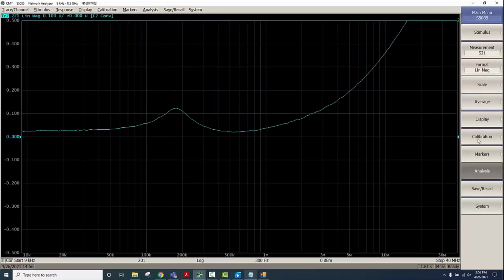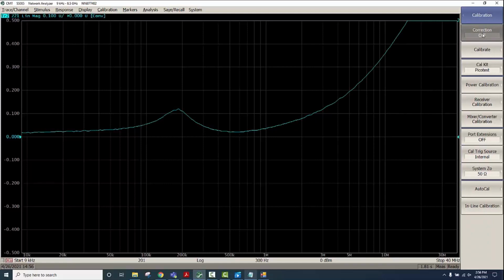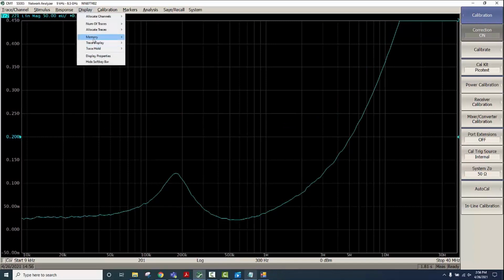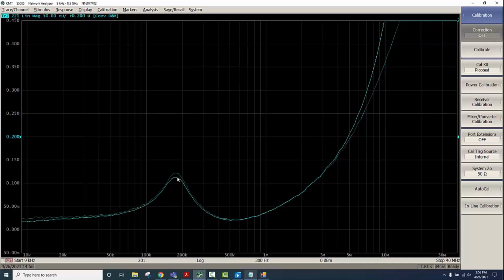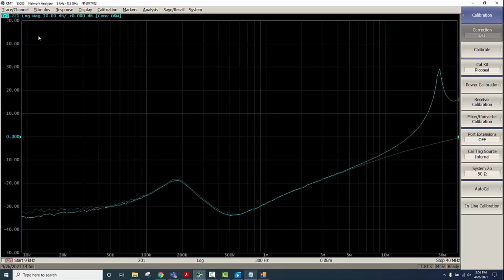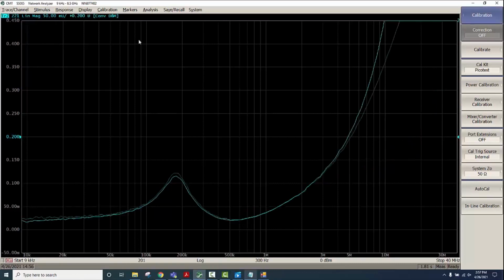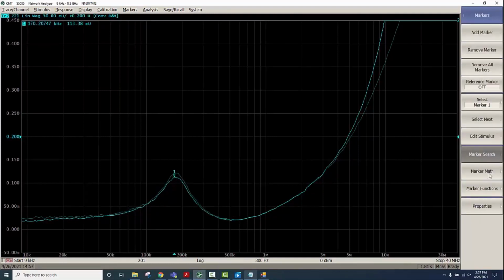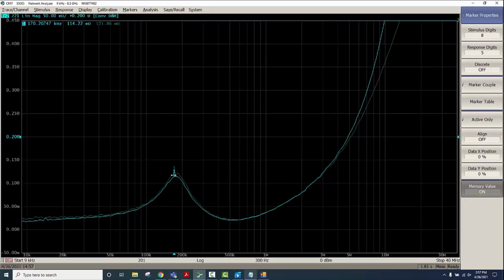We can also look at the measurements with and without calibration. So this is with correction on, so we'll put this to memory to just compare, and then we'll do correction off. You can see there is some small difference there. We can also zoom in and see how the measurements would look like in either the log scale or the linear scale. I can add a marker and see that there is some small difference here. At the peak here, as well as at low frequencies, as well as at high frequencies.